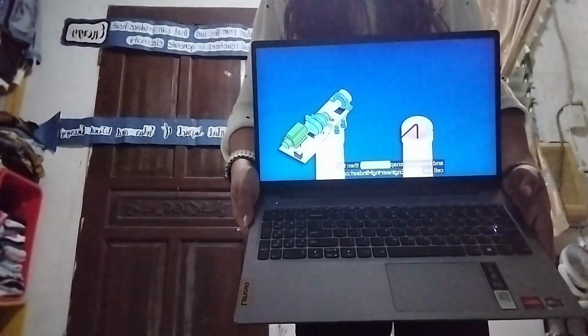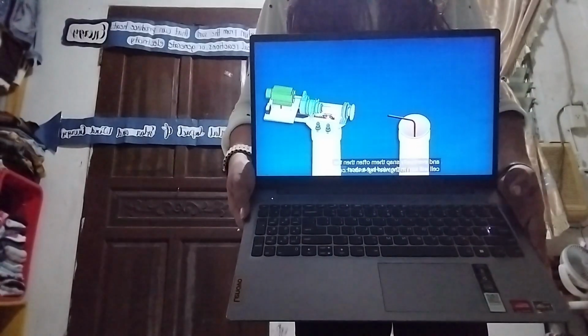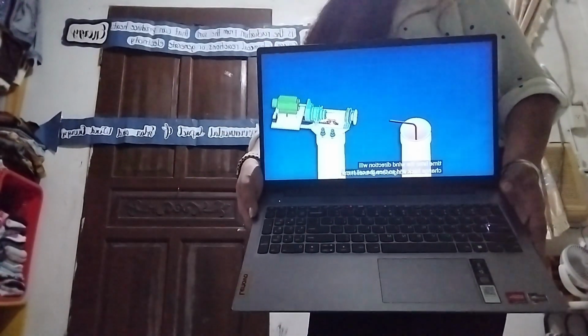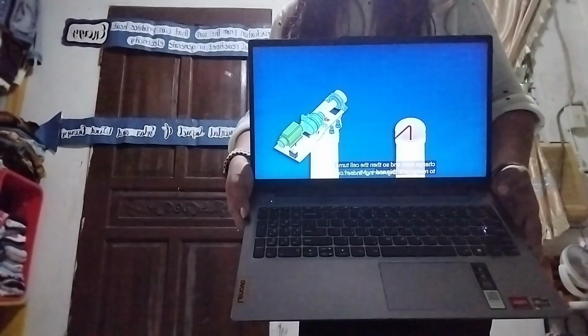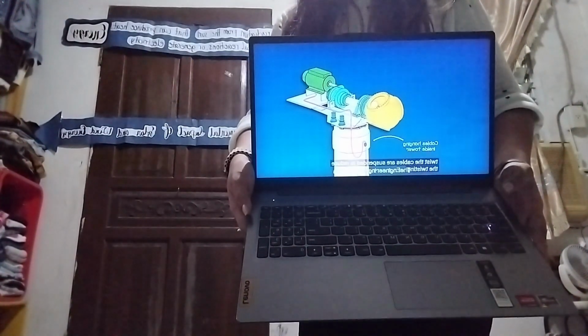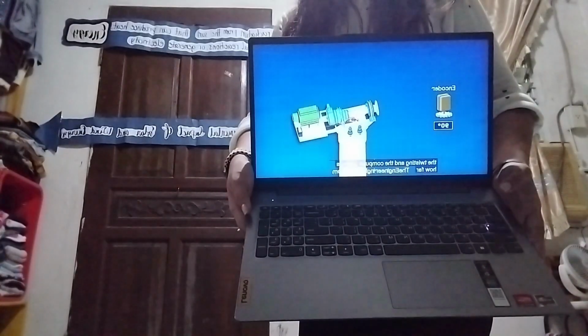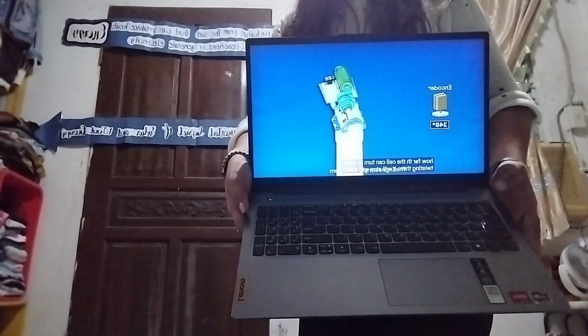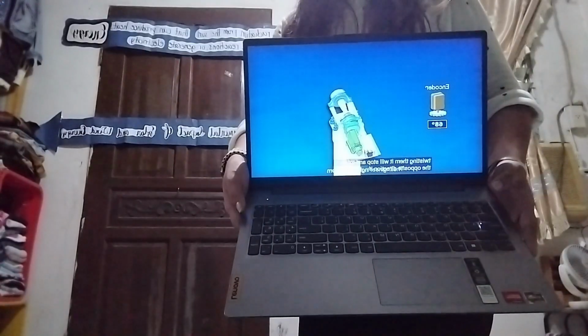Often, the nacelle will turn in the wind, but a short time later, the wind direction will change back, and so the nacelle turns to realign with this and undoes the twist. The cables are suspended to reduce the twisting, and the computer controls how far the nacelle can turn to avoid twisting them. It will stop and rotate in the opposite direction if needed.